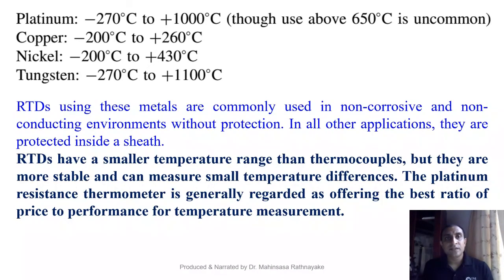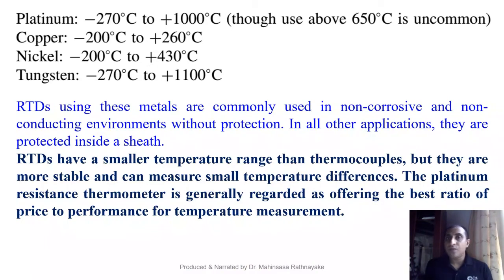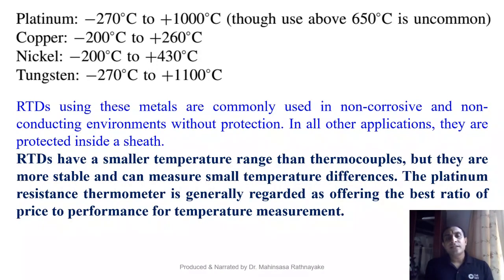From existing findings, RTDs manufactured using platinum have a measurement range of around minus 270°C to 1000°C. Copper has a limited range of minus 200 to 260°C, nickel is minus 200 to 430°C, and tungsten gives a larger range of minus 270 to 1100°C. RTDs using these metals are commonly used in non-corrosive and non-conducting environments without special protection, because there is no threat of corrosion or decay of the metal element.